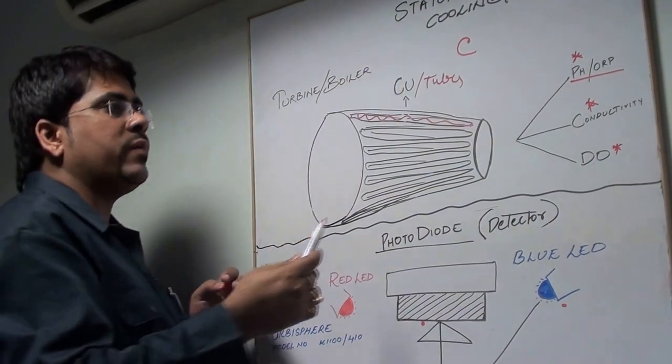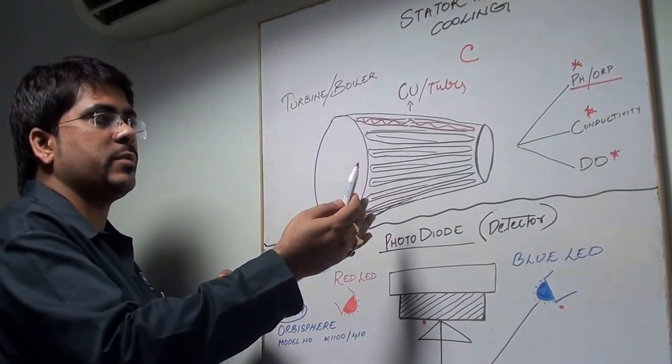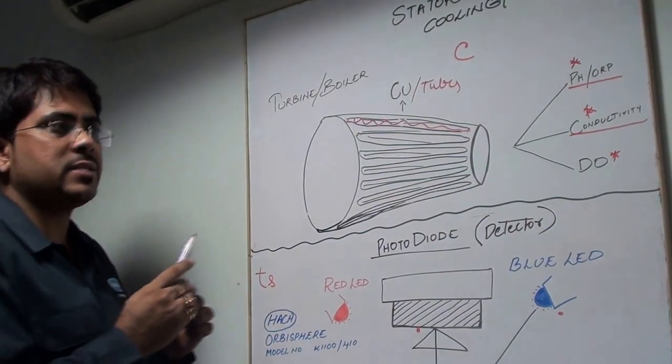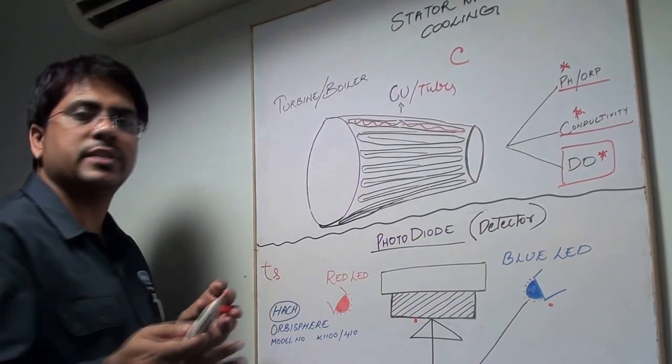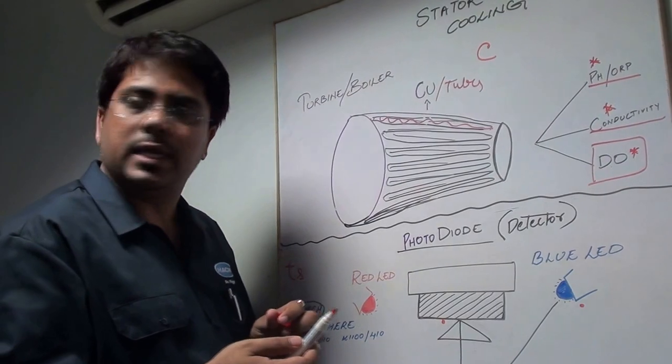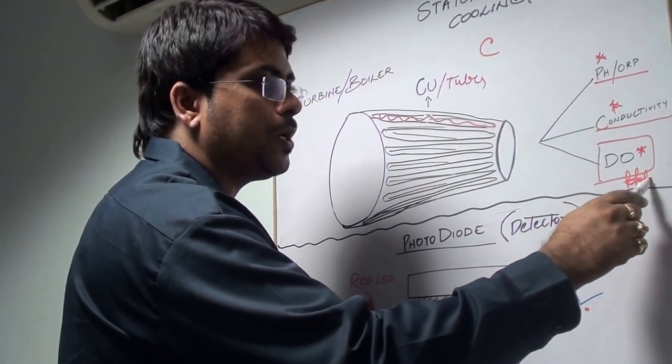Whether there is any leakage or other chemicals getting contaminated, we should measure conductivity. But last but not least, the most important measurement I just explained is dissolved oxygen in the range of PPB, very low parts per billion.